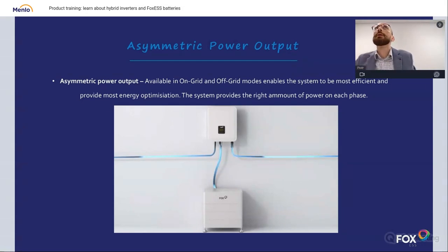And a few words about asymmetric power output, because that's really important, really needed for off-grid operation. This means that if you have a three-phase unit, it will work in asymmetric mode. You can turn it off, but it will turn your hybrid inverter from hybrid operation to on-grid operation, and you will be downgrading your system, to be honest.